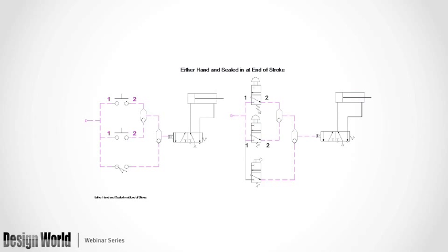But here's the symbol. It comes in. I push down this valve. I will have continuity between 1 and 2. I'll push this down. I have continuity through here, and it will push the valve over. When the cylinder is fully extended, it's going to hit this one. Air will come down and latch on. So you see the difference between the two symbols.